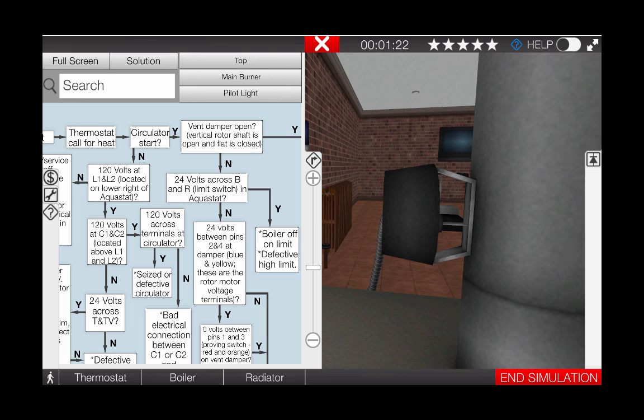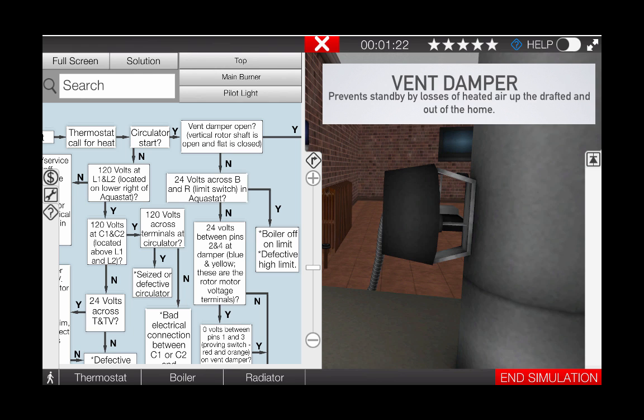The vent damper is a motorized damper that closes off the flue passageway on each off cycle, preventing standby losses of heated air up the draft diverter or draft hood and out of the home, and is an important energy conservation addition to any atmospheric gas boiler.